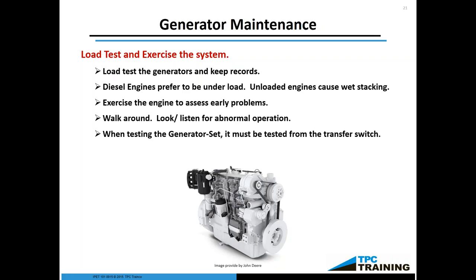Allow the coolant to pass all the way through the engine, the fuel to be pumped from the tank through the fuel management system, through the engine — and this entire time you're observing and listening to all these processes. Look for water leaks, fuel leaks, check the oil. That's why they say run it for 30 minutes — to give you adequate time. Walk around. Look and listen for abnormal operation. Use your senses. You don't have to touch it while it's running — you can just go up to it and listen. If you hear a strange rattling, you need to investigate. Is that something that needs to be tightened? The code requires you test it from the transfer switch or the point at which your backup system calls the generator. Also check the fuel consumption and fuel quality.